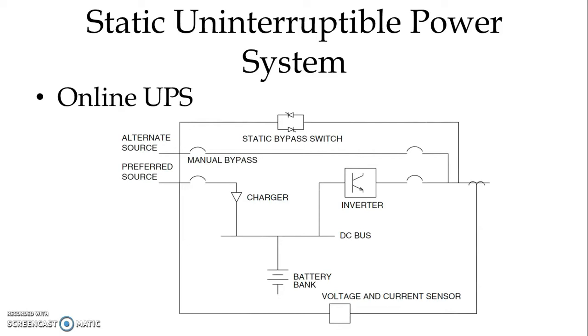Now in case of online UPS, the supply is always through the inverter. So we have preferred source, and through the source we are continuously charging the battery through the rectifier. Rectifier as well as inverter both are connected to the DC bus, and inverter is taking power continuously from the DC bus, and it is converting into AC power suitable to the load, and then it is feeding supply to the load. So it is always through the DC bus, and we have certain advantages also.